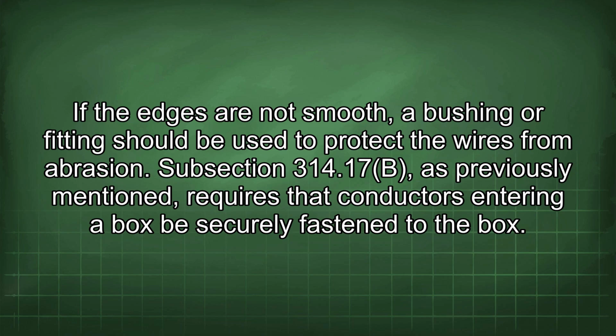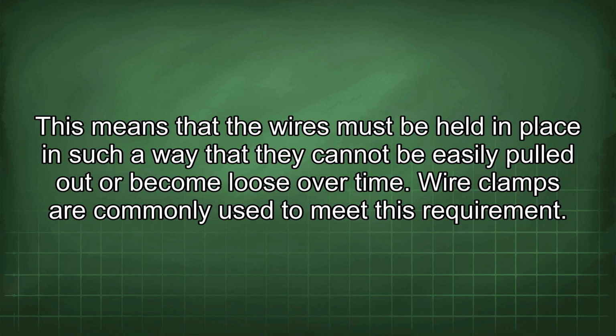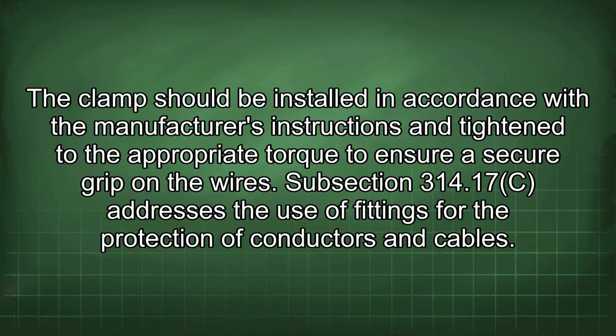Subsection 314.17b, as previously mentioned, requires that conductors entering a box be securely fastened to the box. This means that the wires must be held in place in such a way that they cannot be easily pulled out or become loose over time. Wire clamps are commonly used to meet this requirement. The clamp should be installed in accordance with the manufacturer's instructions and tightened to the appropriate torque to ensure a secure grip on the wires.